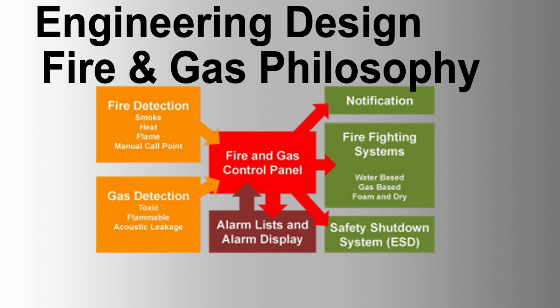The fire and gas system includes hardware and software for powering and interfacing field fire and gas detection and protection devices, monitoring fire and gas alarms from the Central Processing Facility Control Room, implementing executive logic associated with the fire and gas detection philosophy, initiating fire and gas protection devices like deluge valves and extinguishant release valves, activating alarm signals, beacons, and horns, interfacing with PAGA systems, fire alarm control panels, FAP, building fire and gas systems, and other control panels. The system architecture supports a dedicated fire and gas system for central processing facility processes, central processing facility compressors, and central processing facility utilities.